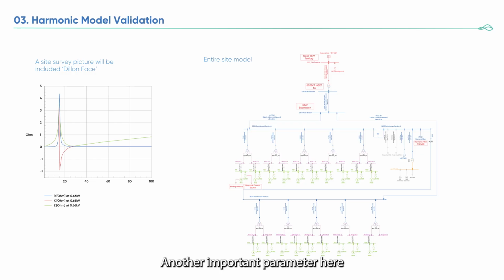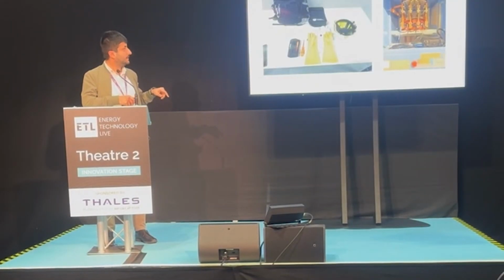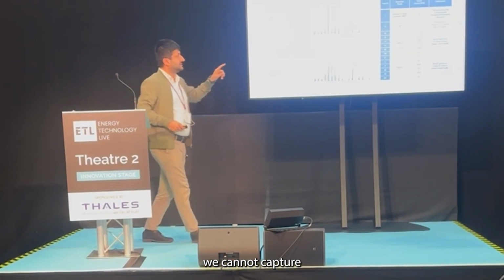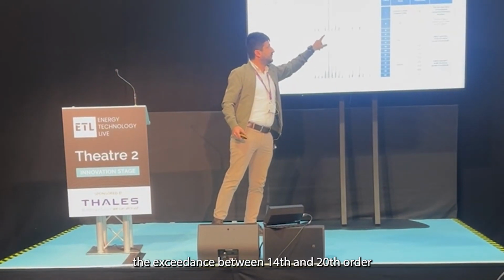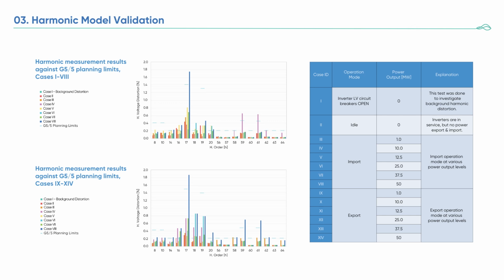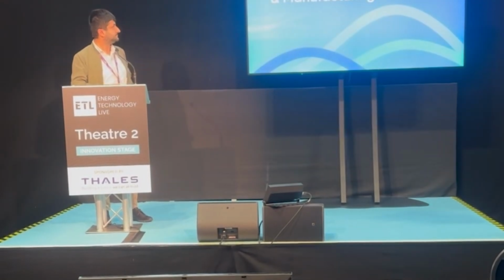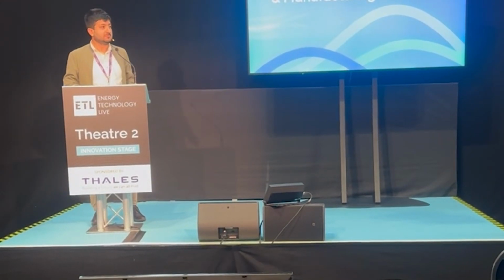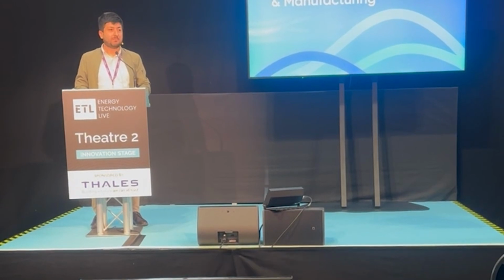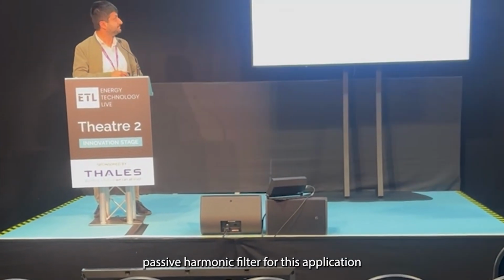Another important parameter here, self-impedance of the inverter. If we do not include this self-impedance of the inverter in our study, we cannot capture the exceedance between 14th and 20th order. So especially this data set is quite important and essential to include in the model for an accurate analysis. We have validated the model, then we have started to design a passive harmonic filter for this application.